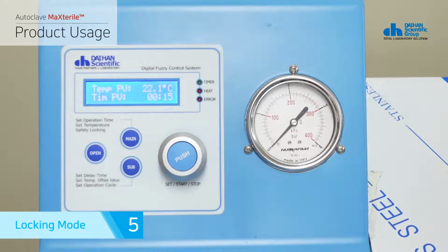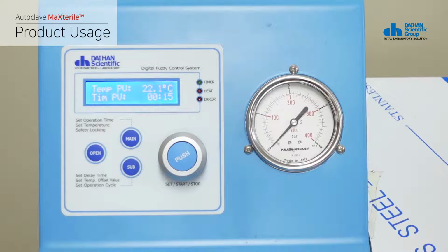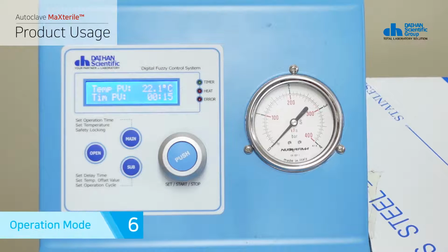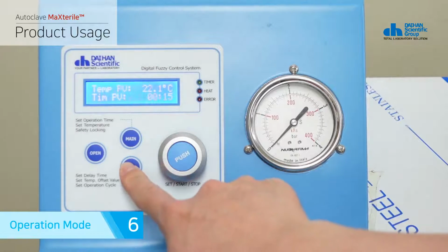Switching to lock mode displays the current temperature and remaining timer time, and the lock mode prevents the recognition of additional commands even if you press jog dial, so stable operation is possible until the end of sterilization.